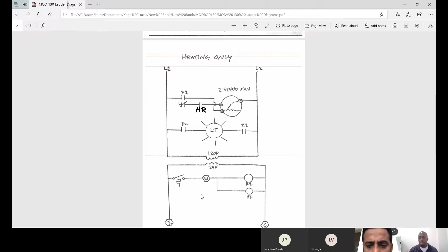If we leave this on auto and we turn on our cooling, then we're going to energize the Y and the G, and the fan's going to come on in high speed. Low speed is different. If I go back to last week's diagram, you'll notice we don't have a G down here at all, because the low speed terminal is energized by the heat relay. The heat relay got its power from W. So low speed only operates when the heat is on.